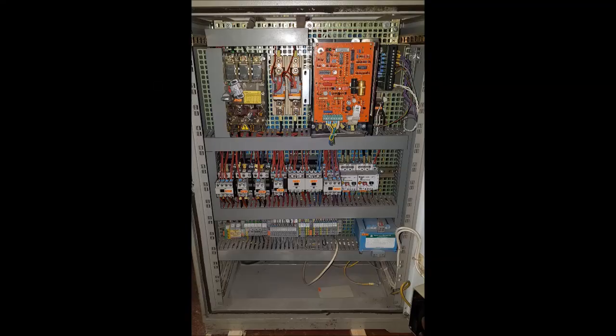And this is the main electrical cabinet. We're looking at 1992 technology here. This is the mechanical main switch, then special fuses to protect the thyristor controller. This controller was made by ABB, and a custom circuit board that does the constant current regulation. On this rail we have some contactors that I'll explain in a bit, and on the bottom there's terminal strips and a control voltage transformer.